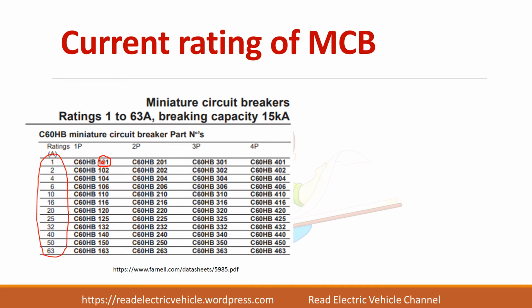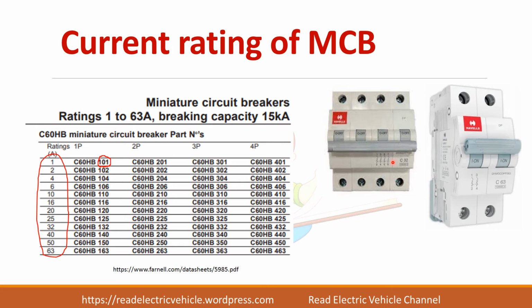Here the last 2 digits represent the current. 63 represents 63 amps, and this one represents whether it is single pole, double pole or triple pole. So you can see here 3, in 4 pole it will be 4. So this is not a standard one, it varies with respect to manufacturer. So you can see here C32 amps and this is C63 amps.